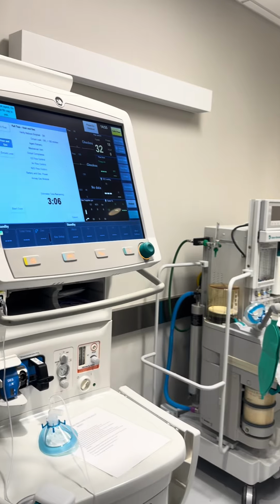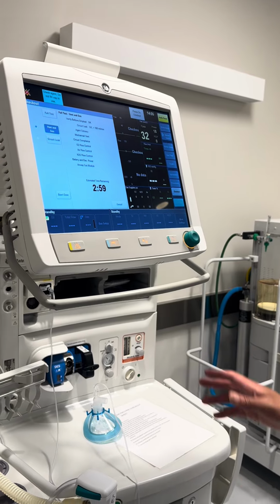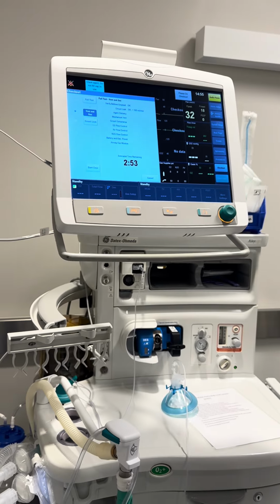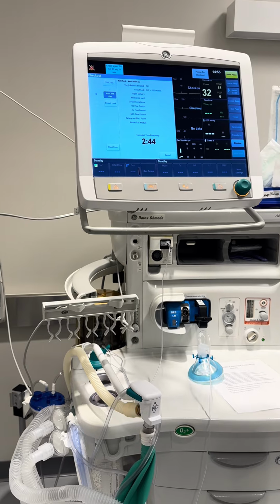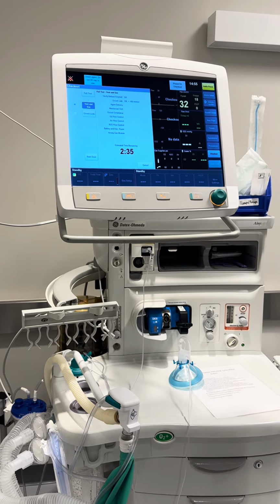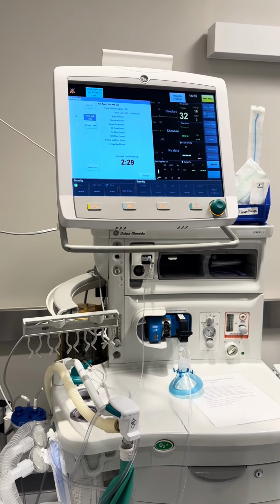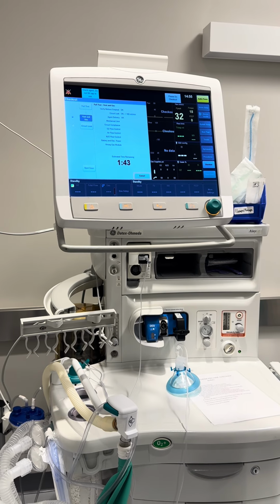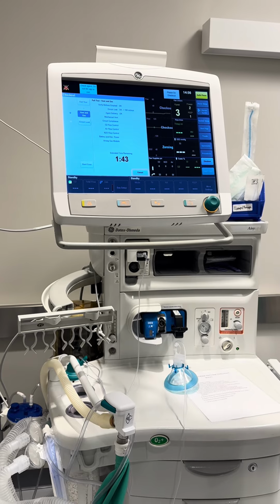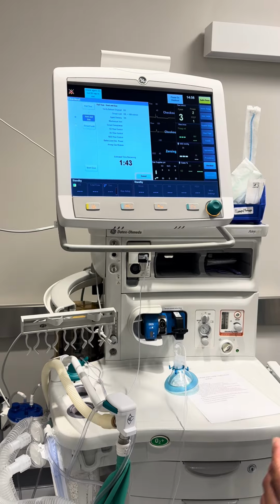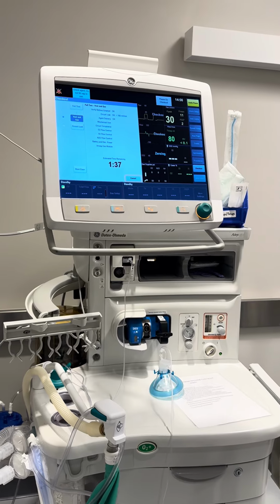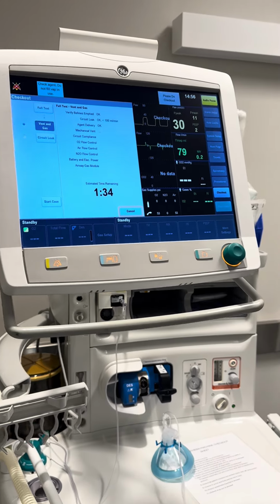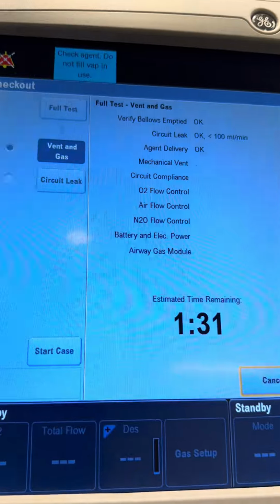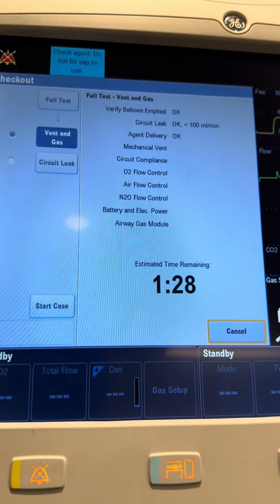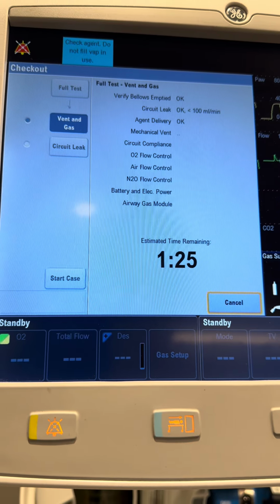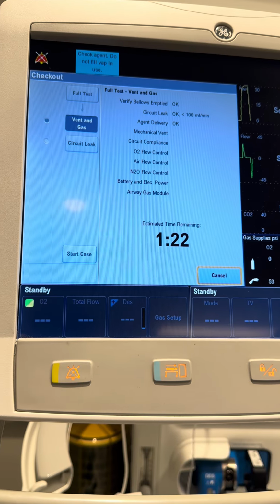So it takes a little bit, just making sure that it's going through all its tests. Right now it's going through the agent delivery, making sure that it's going through the system properly. And this is a very tedious process, but like I said, we want to make sure that the patient's safe. The actual test can take anywhere from, I'd say, 3 to 5 minutes, but 9 times out of 10 it's going to be on the longer side, just to make sure that everything's good. Some of the newer machines, they're really fast, and they can do the machine check in about 2.5 minutes.